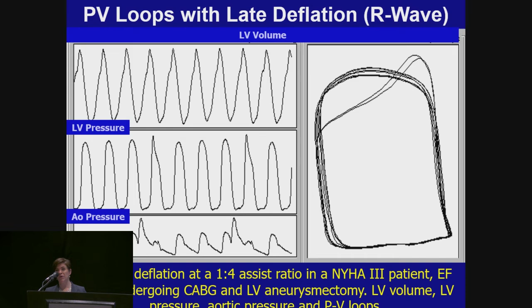Now, looking a little bit further at our deflation timing management with the Aero system, when an arrhythmia is detected, the balloon pump chooses peak trigger to allow the earliest trigger detection point. The pump then measures the time available for deflation, the PEP phase, the distance from R wave to AP upstroke, and the time needed to achieve at least 70% deflation of the balloon catheter. So we don't want anything more than 30% residual volume in the balloon catheter at the start of systole. Therefore, it would be causing a late deflation.